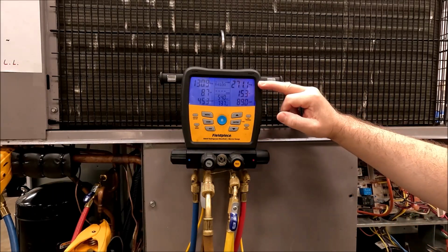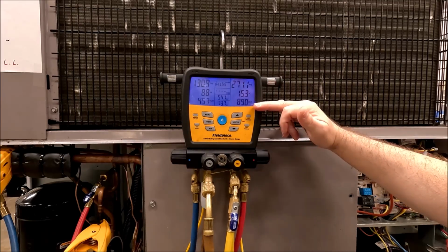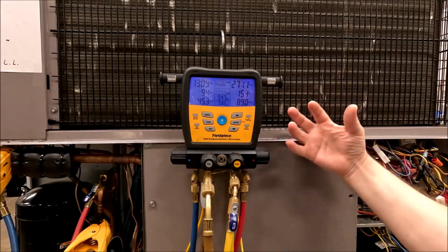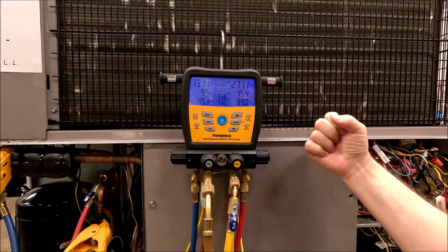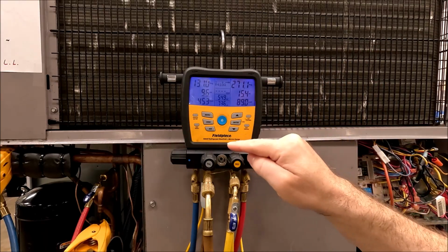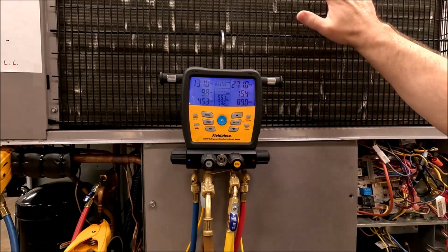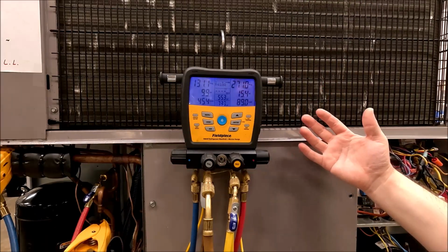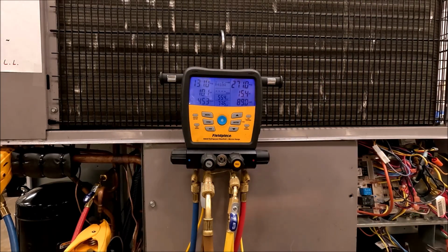271 PSI gives us an 89 degree saturation point on our high side. So this is where we're actually taking enough heat out of that superheated vapor in the discharge line. It gets into the coil, and we turn it back into a liquid. So that's the point.